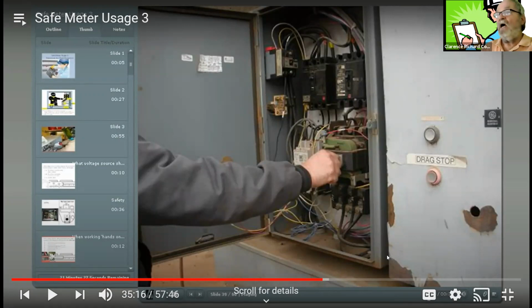A lot of times, the most dangerous moment when starting up equipment is when you do it for the first time, when you're first wiring things up. First of all, you don't know if you're wiring up a shorted load or not. You don't know if it's really wired up correctly. So when starting up, I was working with the electricians at the time, and you would hear them communicate with each other: this is a first start.